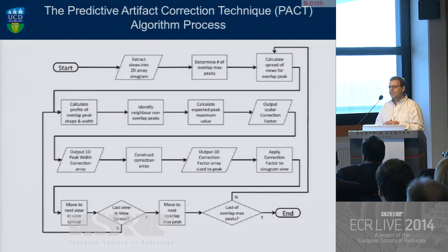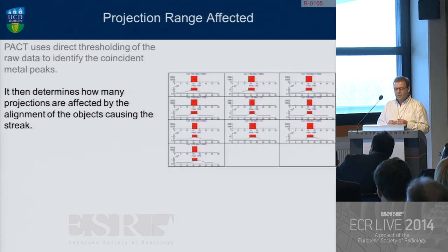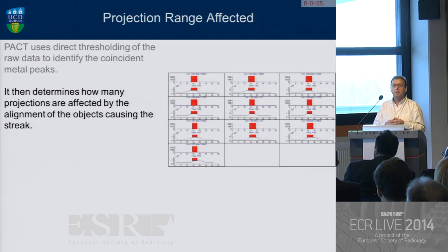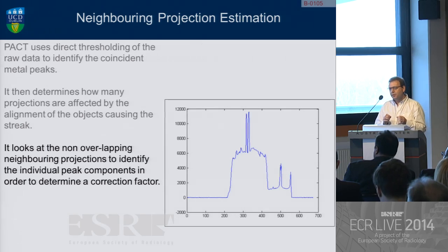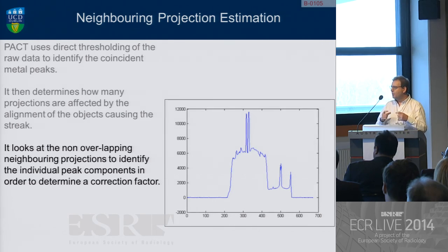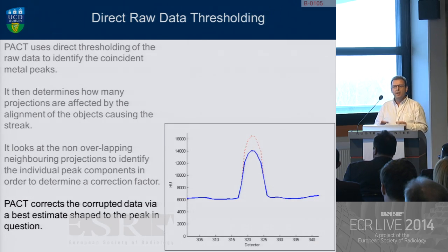This is the PACT algorithm — predictive artifact correction technique — that I wanted to work on. I'll take you through it visually. I use a thresholding technique to actually identify the metallic coincidence events within the raw data. We then analyze the projections for the entire overlap, because this may happen over a degree or two degrees, so quite a few projections may be contaminated. We also analyze very carefully the shape of the peaks, because they're quite skewed as the objects come into alignment and then go out of alignment again. Then we step very slightly to the side of the coincidence event, and we can actually see the separate objects just before they come into alignment. At this stage, we can identify what the individual components are, predict what the value should be from the reconstruction process, calculate a correction factor, and apply that correction factor in correlation with the shape of the peak — whether it's slightly skewed or in perfect alignment.